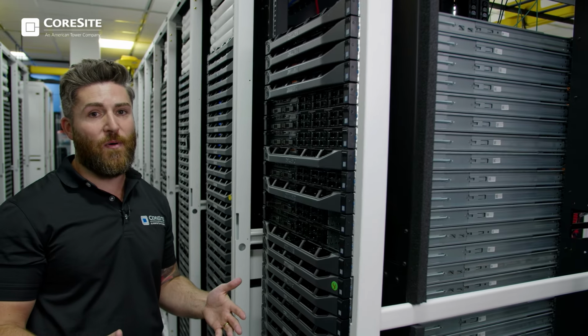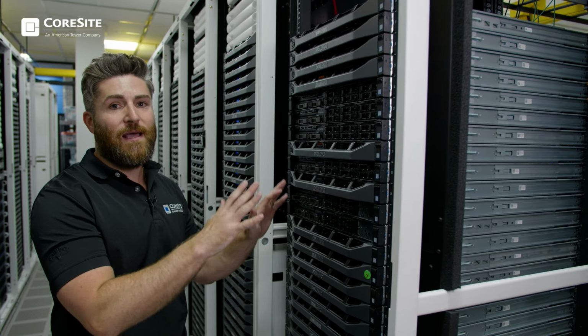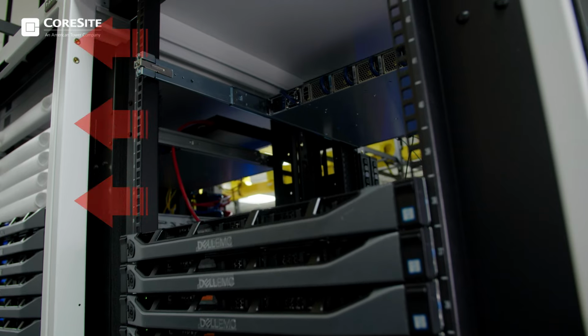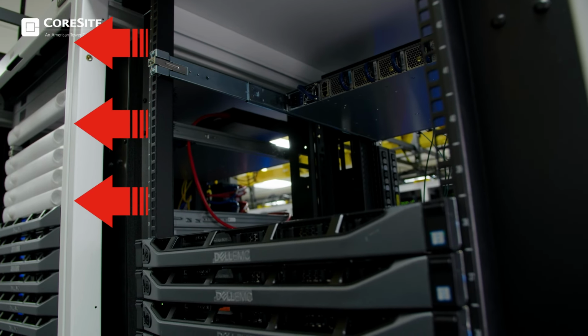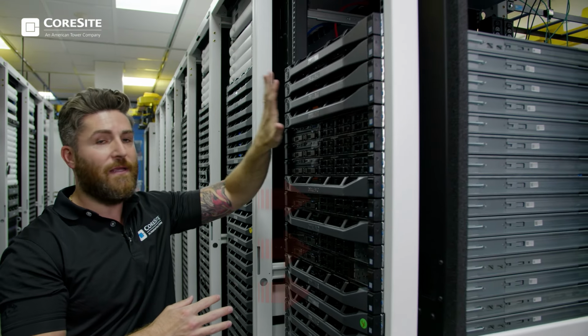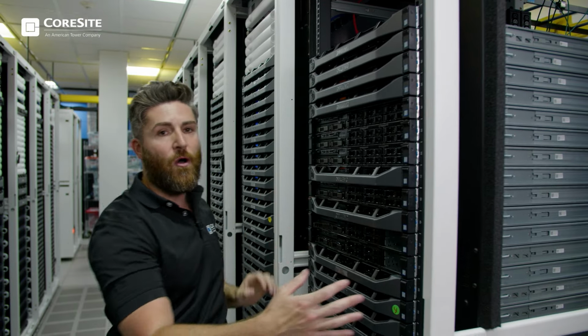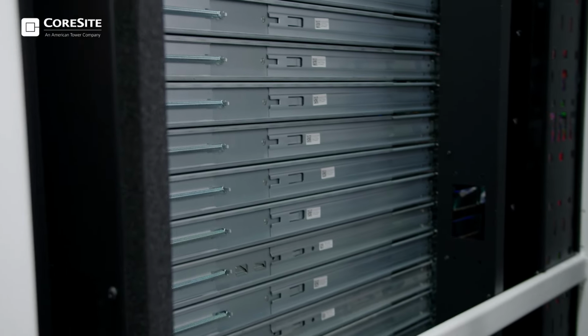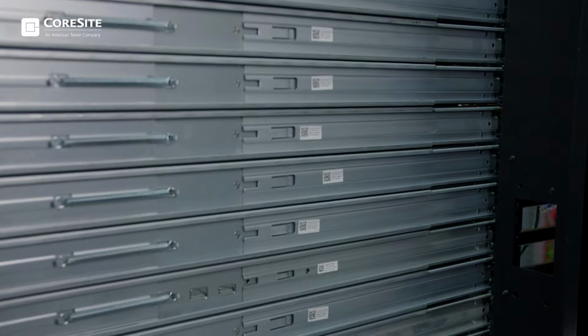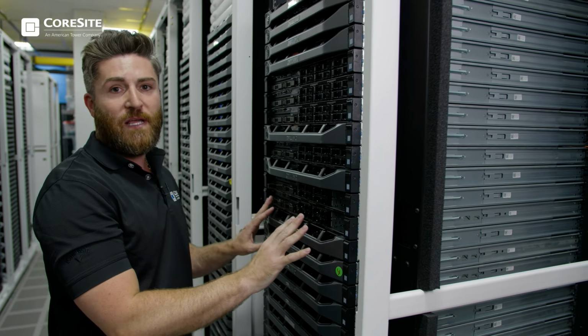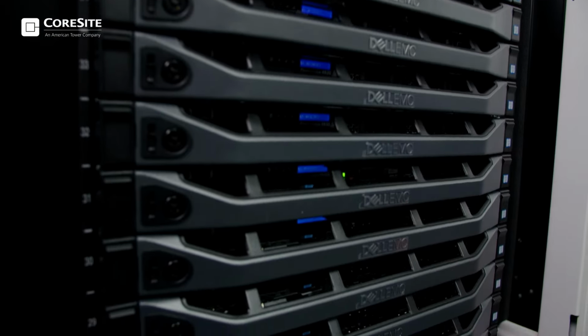This is a good example of a cabinet that has not yet been optimized. There's hot air coming potentially from the hot aisle through the cabinet into the intake of this server, and also on the side as well, causing a whole bunch of unwanted heat in this section of the cabinet and potentially damaging the servers.